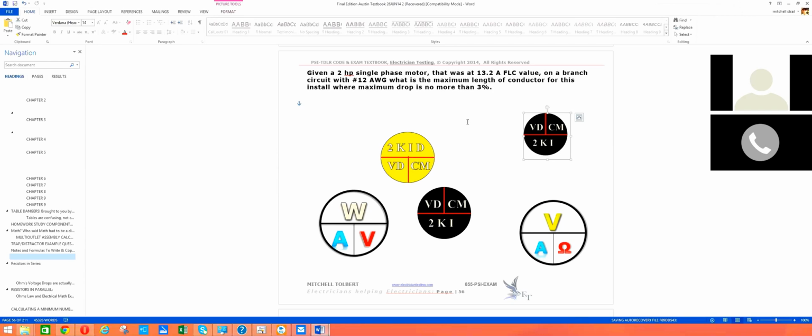Yeah, two-phase. So what you're going to use for this test, and pretty much in the trade even, is going to be the 248, which is on the left-hand side, the smaller table for single-phase motors, and then your three-phase table will be the one on page 351 to your right there on the top. There, I see it. Okay, yeah. All right, so two-phase doesn't work.